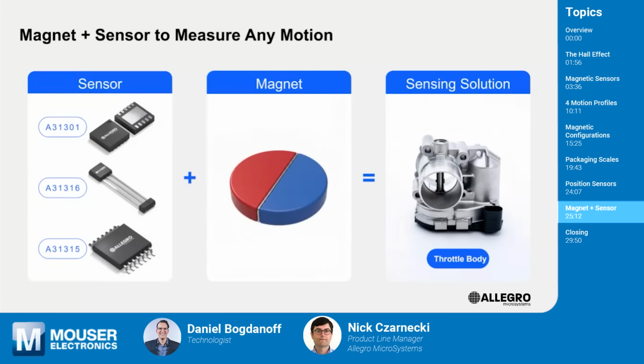What this slide showcases is that it's very easy to integrate these devices—really just sensor plus magnet and you're effectively done. Obviously I'm simplifying a bit; there's things like programming the desired output span. These devices are typically calibratable at end of line to minimize the amount of angular measurement. For a throttle body measuring 0 to 90 degrees, you want a 0 to 100% output span—you don't want to measure 360 degrees because that valve doesn't spin 360. So these devices are programmable, which makes them very flexible. You can fit the sensor to the application rather than fitting the application to the sensor. These really excel at standalone operations like throttle bodies, valves, or general purpose actuators.